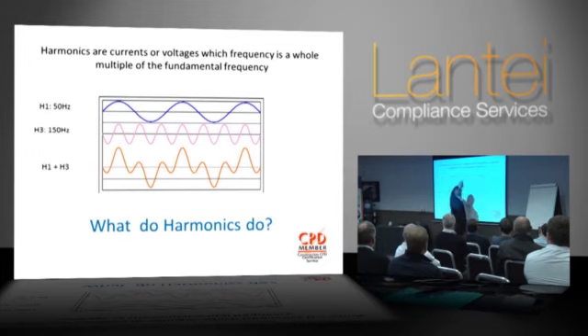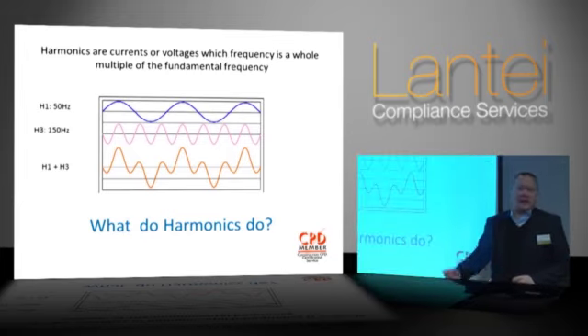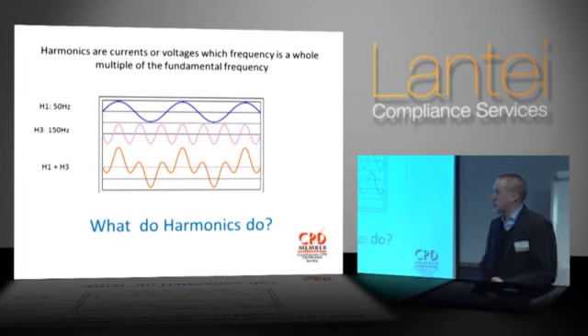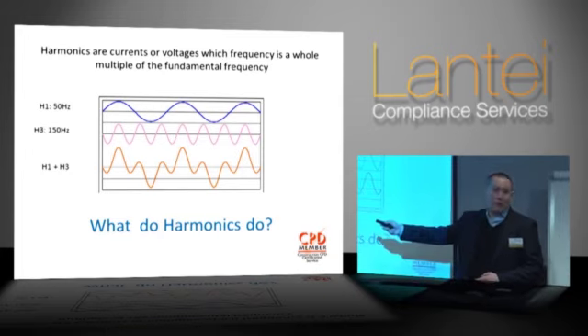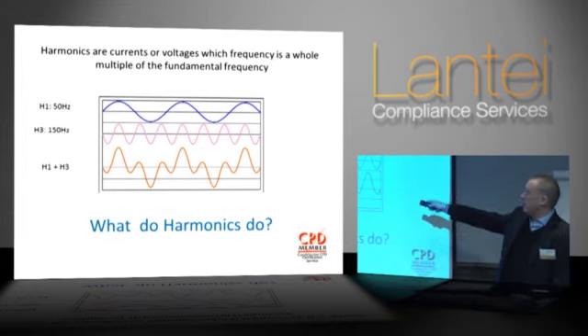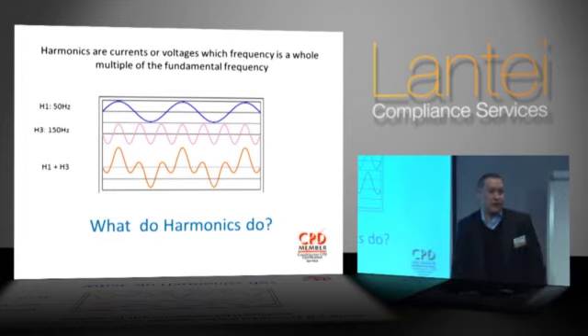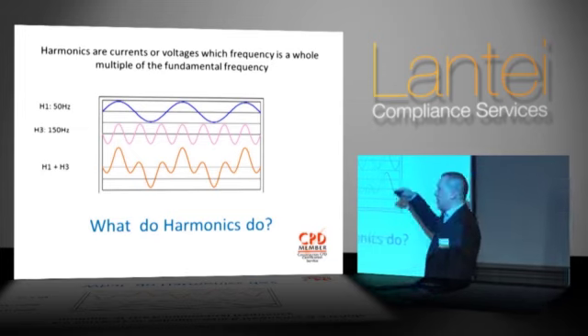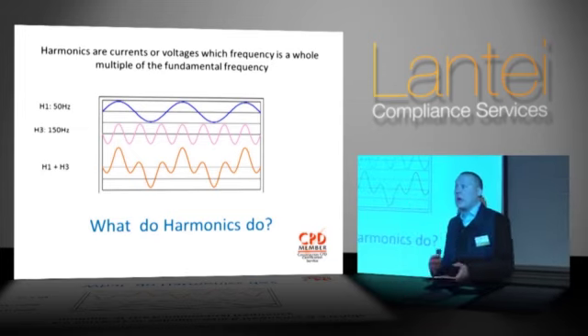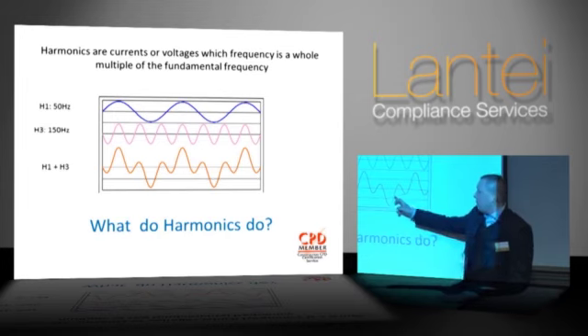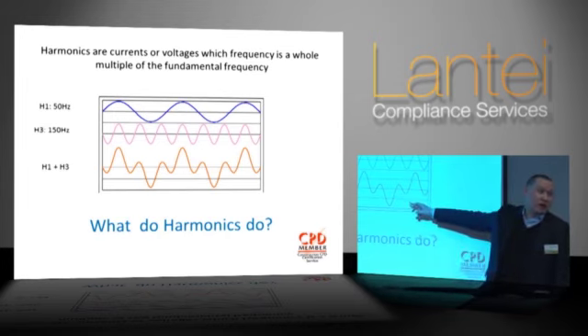And that's what a 50 hertz waveform would look like on a graph. When we've got harmonics issues within electrical installations, just as an example, we'll look at the triplen, the third harmonic. What that means is that our frequency is multiplied by that number. So 3 times 50, 150 hertz. 150 hertz would look like that on a graph. But the problem we've got is when those frequencies start to be added together, which is what we get with harmonic distortion issues, that is the net result of what our graph would look like.